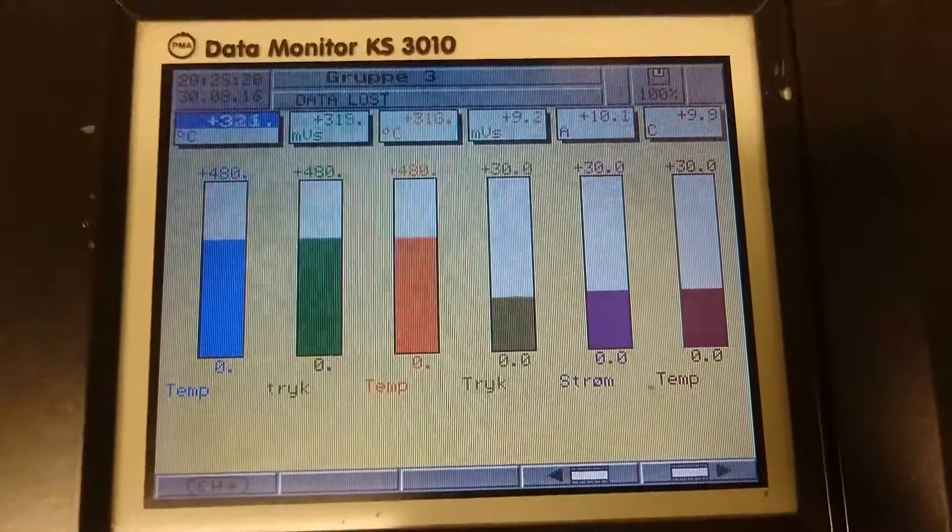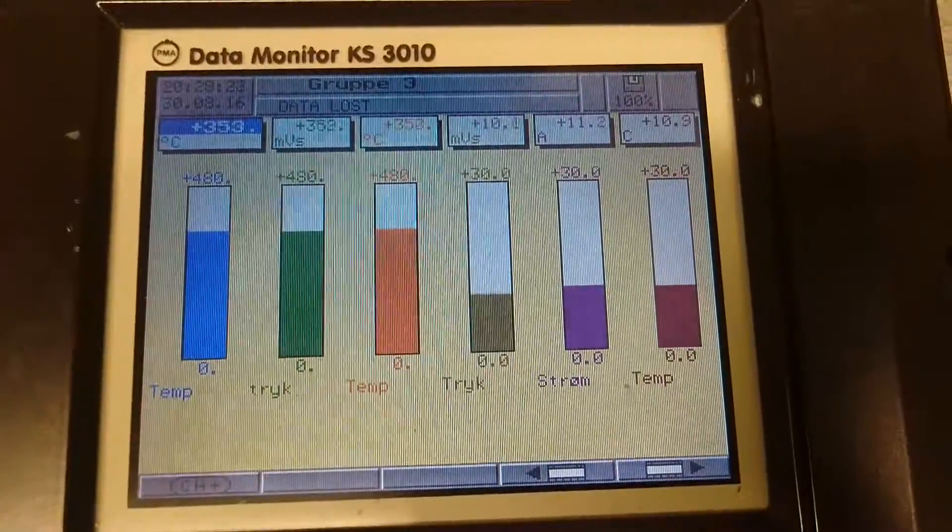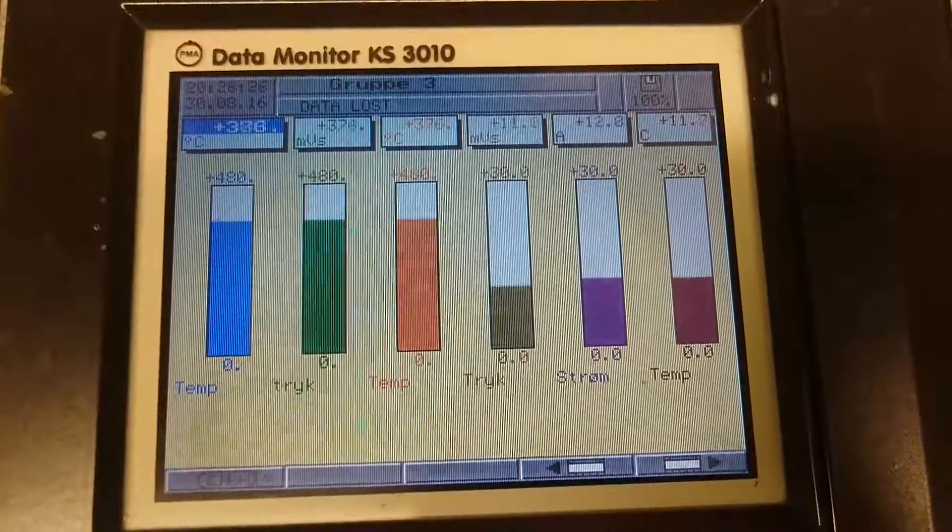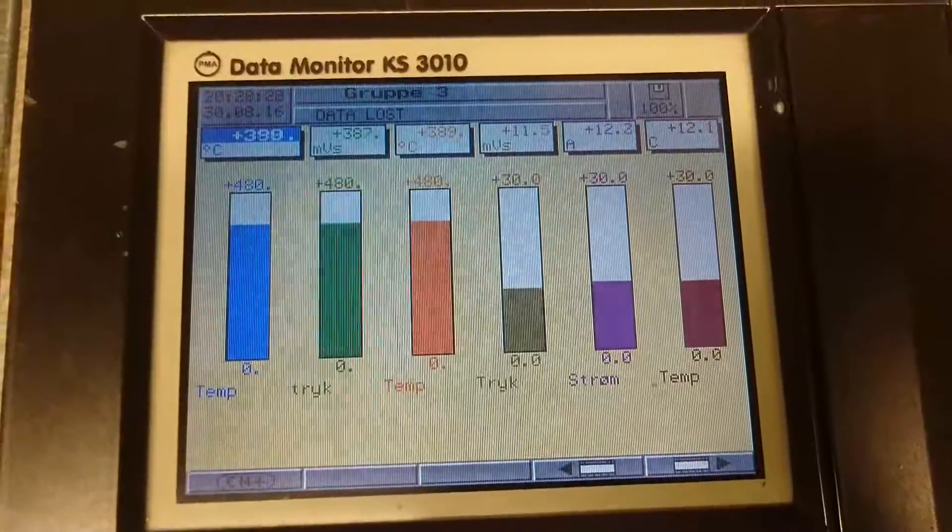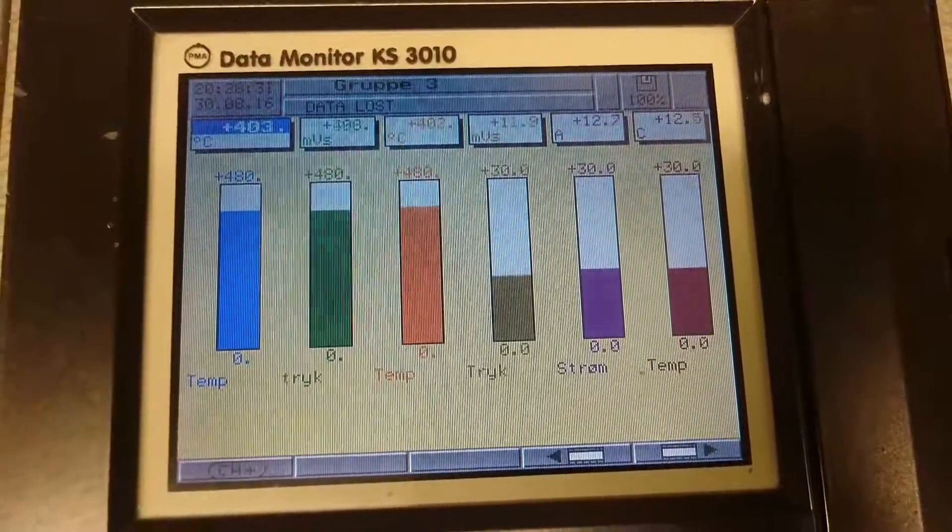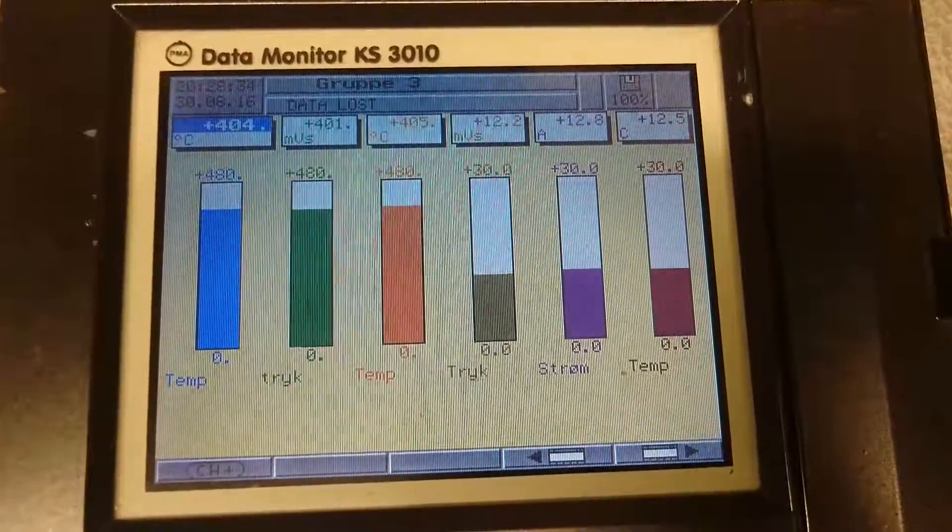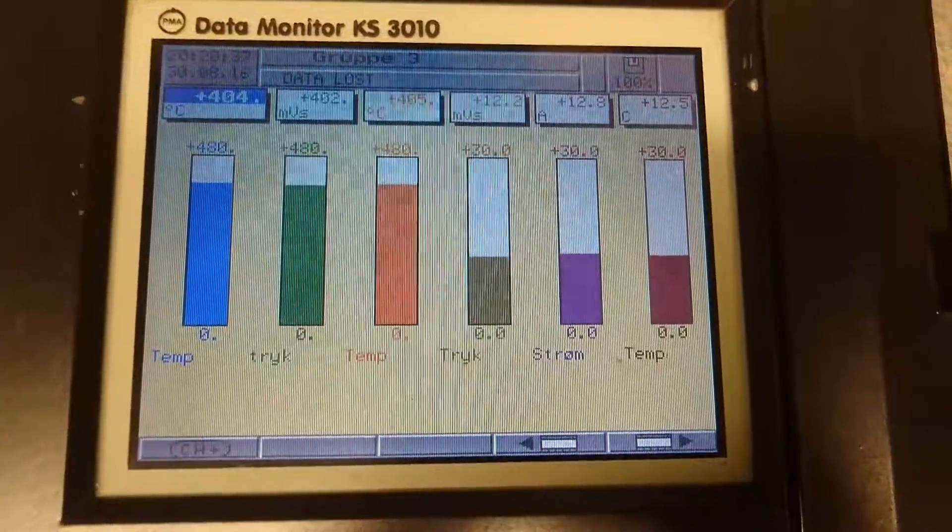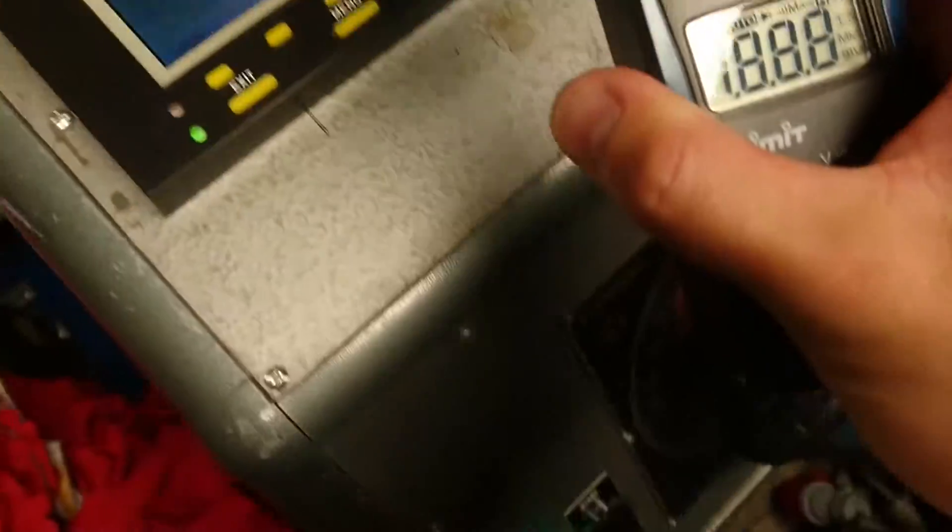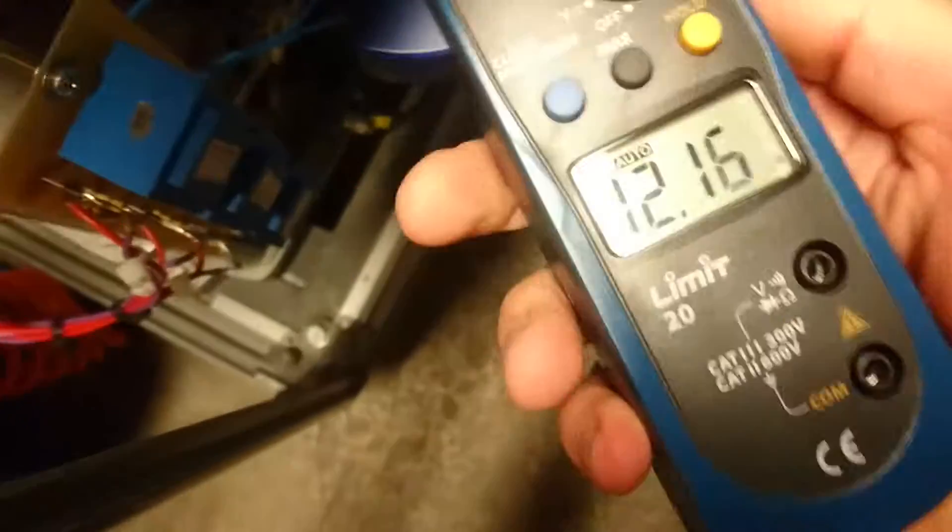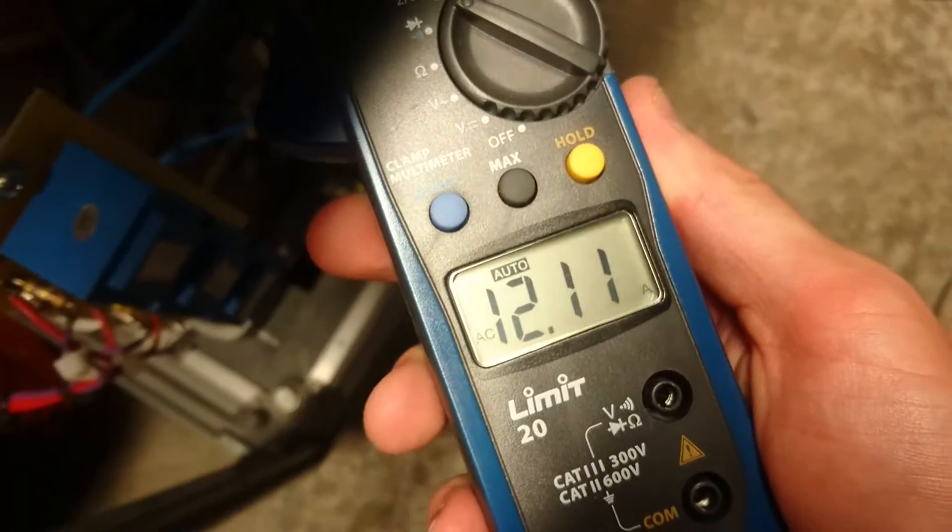So, as soon as I hit 400V AC, I should have around 12A current draw on each phase. And, as we can see right now, we have 12A on each phase. And we can just do a quick control measure down here. If we check this phase, see we are at 12A.